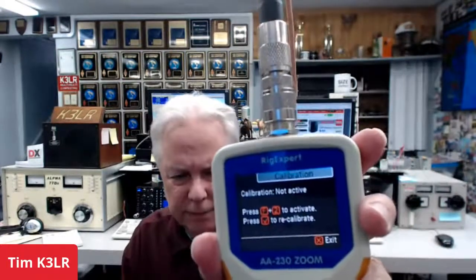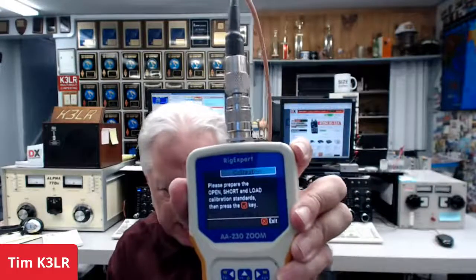All right. So we're setting it to calibrate. Calibrate. All right. And so we say yes to that. And it says the calibration is not active. And it says press F2 to activate, or press the check mark to recalibrate. So we're going to recalibrate. We don't have a calibrate, so we're going to recalibrate. Here we go. So we press the check mark, and it says, please prepare the open, short, and load calibration standards. Then press the check mark.